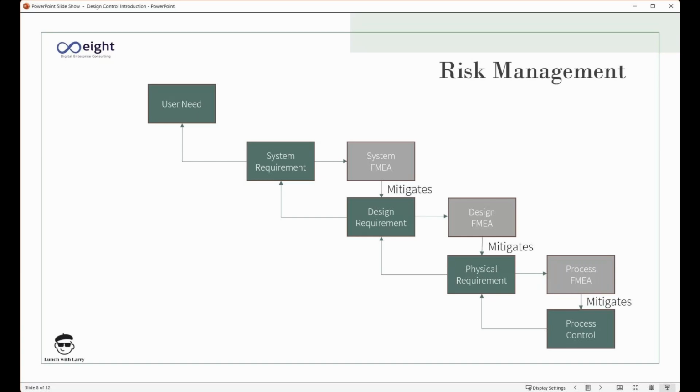And if we do this properly, those FMEAs become part of the mechanism for us to assure that the requirement set is complete. There are many different ways to do this, but one of the things we want to talk about is how we get those FMEAs integrated into the process so that when we do an FMEA, it's not a spreadsheet on a side project sitting in a repository someplace that never gets updated. It should be part of the live data understanding of how the thing's deployed.